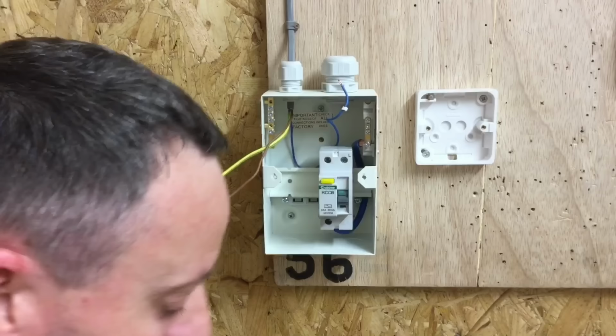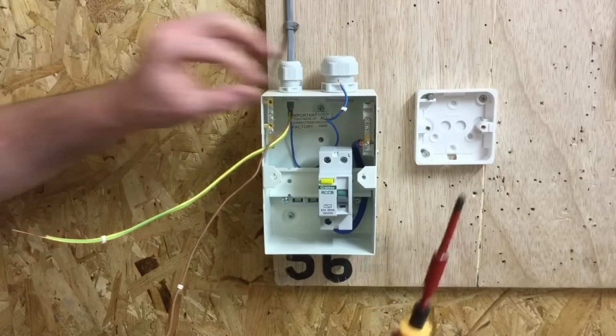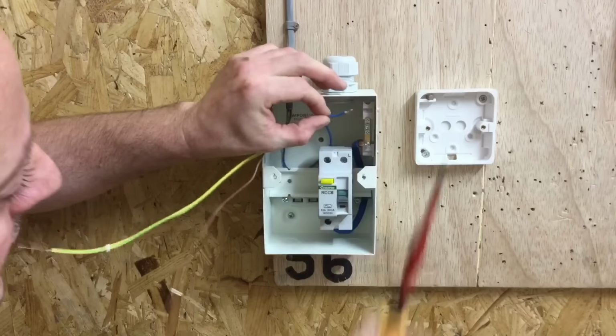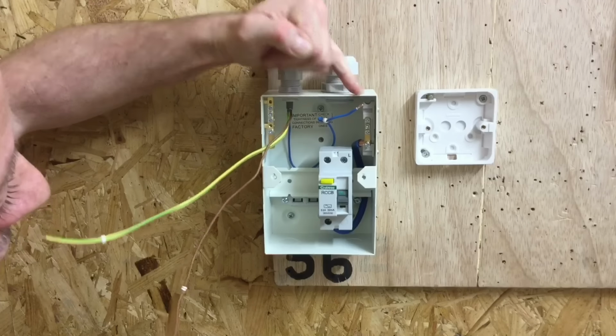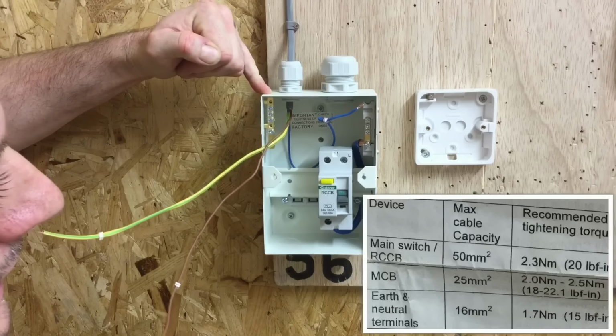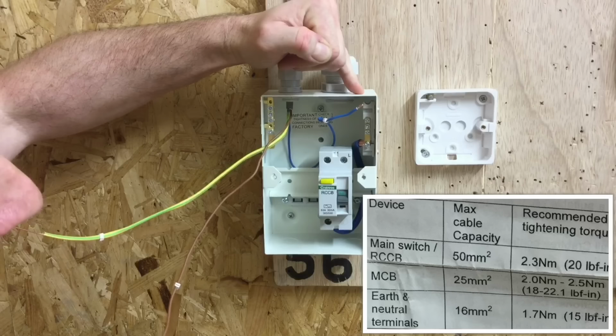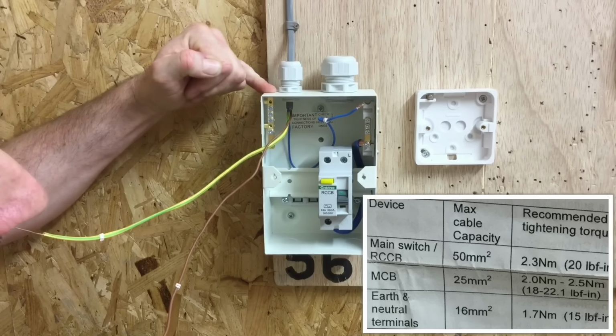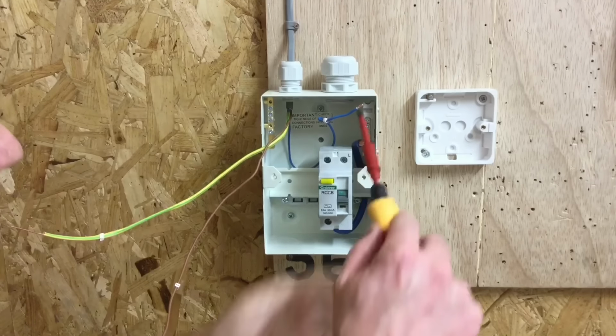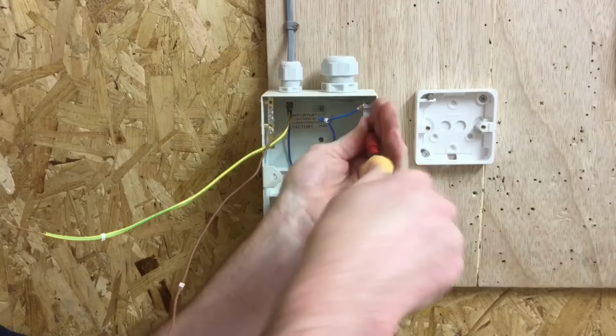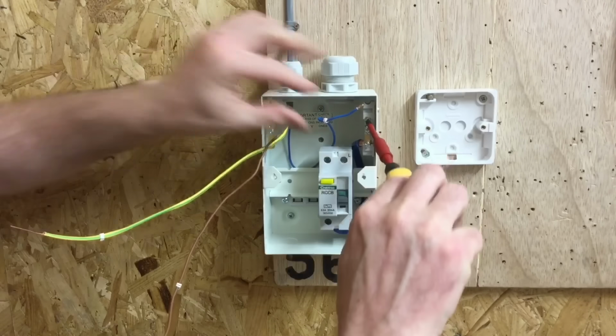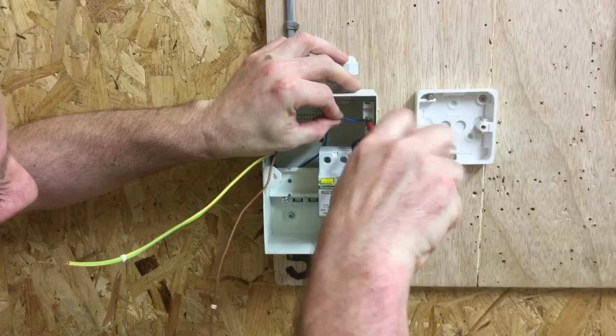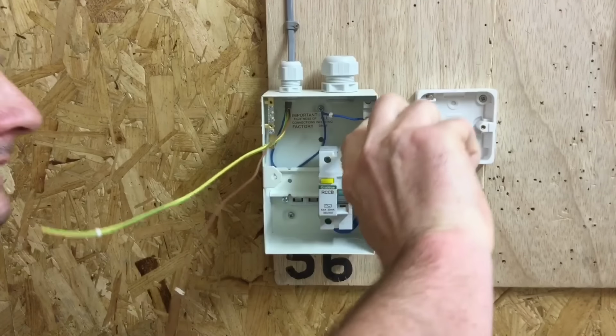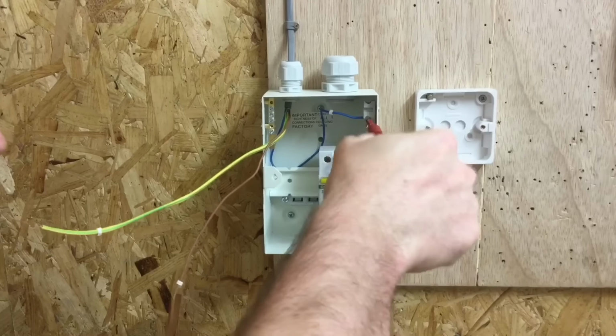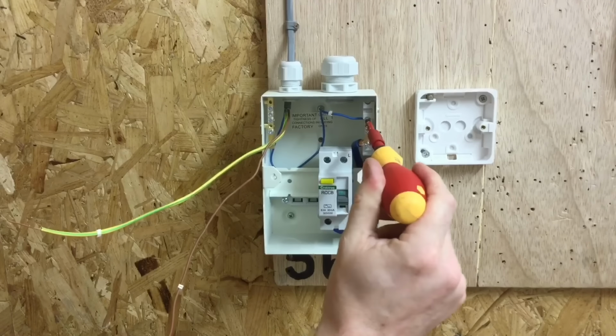So I've doubled over my termination. I've got my torque screwdriver set to the appropriate Newton meters of torque for both the neutral and earth bar. So in this case, it is going to be 1.7 Newton meters of torque for these. So I'll undo the top termination. Position my neutral into the connection and hopefully we get it to tighten up correctly. And we're at the appropriate torque setting for the neutral.